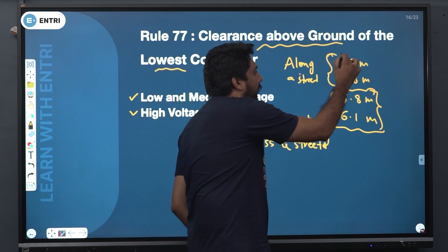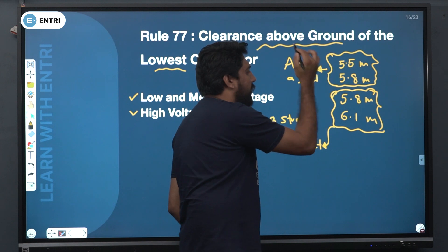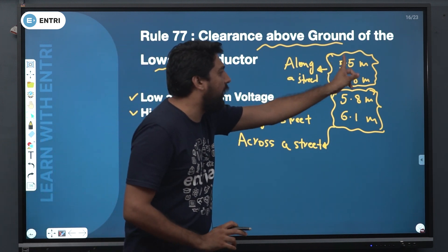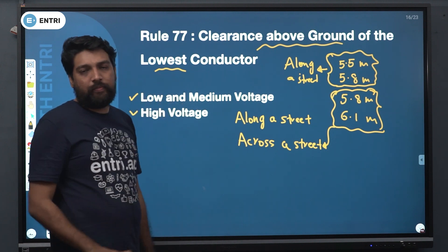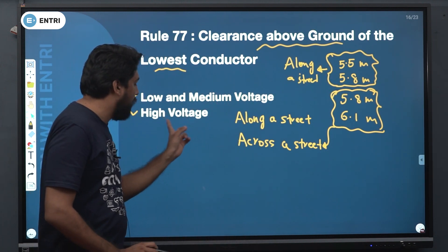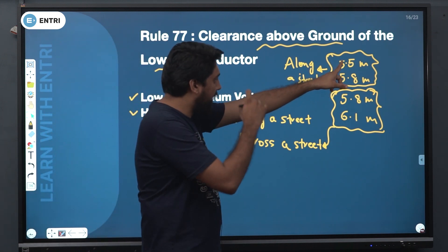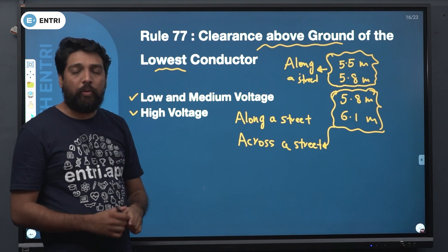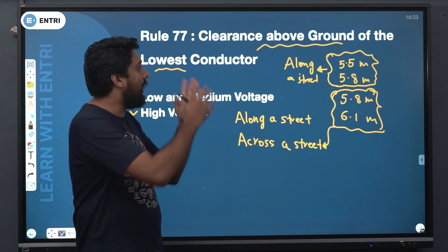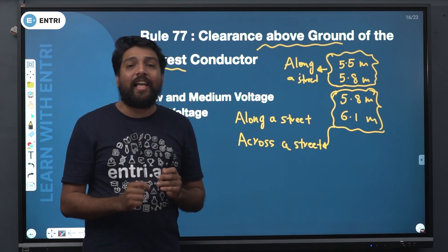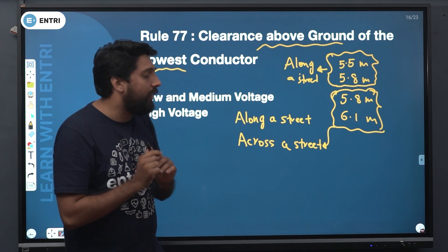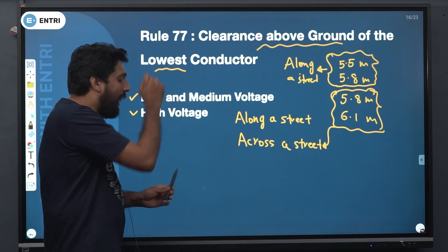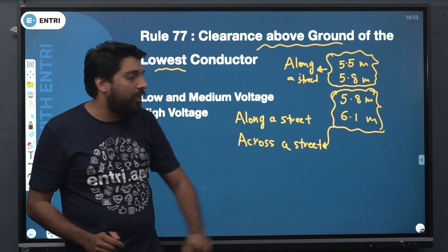So 5.5 and 5.8 relate to along a street. The value 5.5 denotes low and medium voltage; 5.8 along a street denotes high voltage. Along a street: 5.5 for low and medium voltage line with clearance above ground of the lowest conductor is 5.5 meters. In a high voltage line along a street, the clearance above ground of the lowest conductor is 5.8 meters.